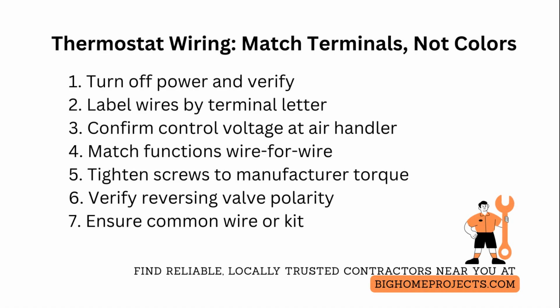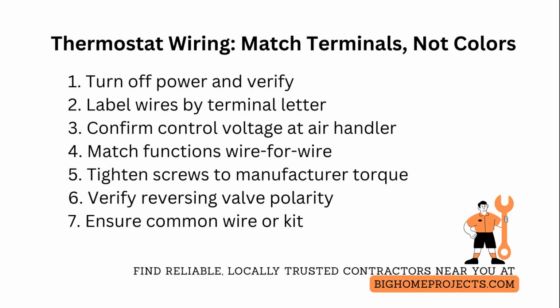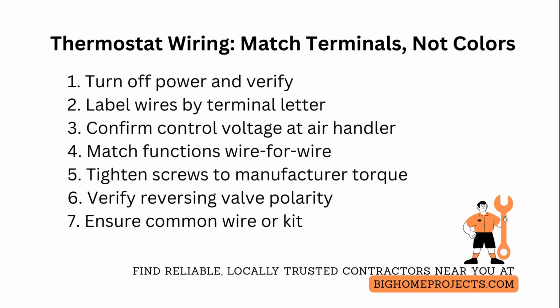Label each wire with its terminal letter, not its color, by removing the thermostat plate and noting exactly which terminal screw each conductor was under. Take a clear, close-up photo and transcribe letters to a paper checklist before disconnecting anything.